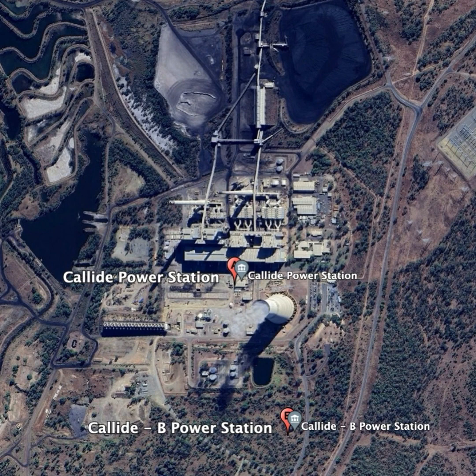Stanwell Power Station, Units 1, 2, and 4 all tripped on low system voltage, and further north, the Townsville gas turbine ramped itself down to 0 megawatts. All of the 275 kV lines out of the Callide substation tripped at their respective remote ends. The Callide substation feed breaker, number 854, from Unit C4 opened, finally isolating the generator from the substation. Unit C4's final motoring load was measured at 57 megawatts pulled from the grid before the substation eventually tripped, after which it slowed and stopped.